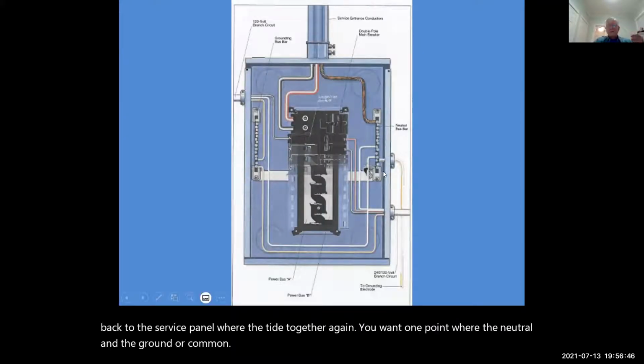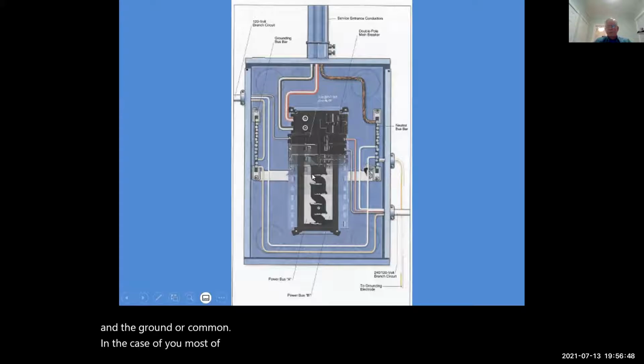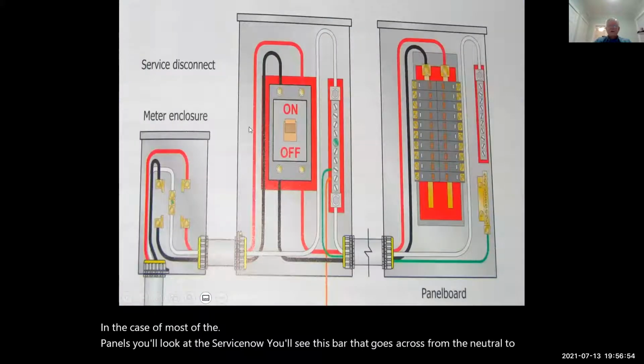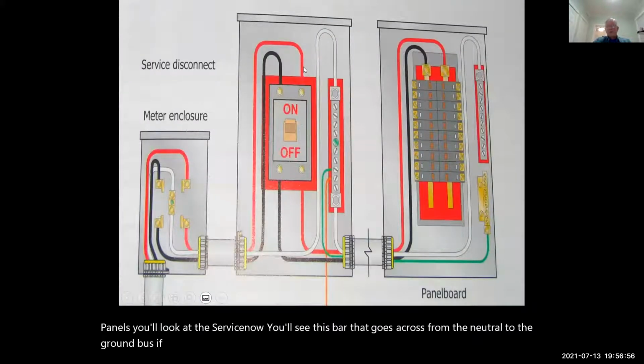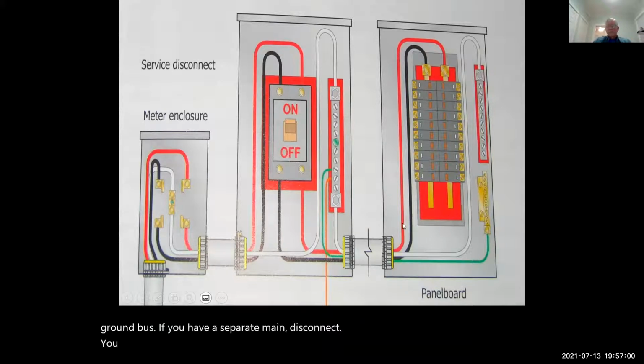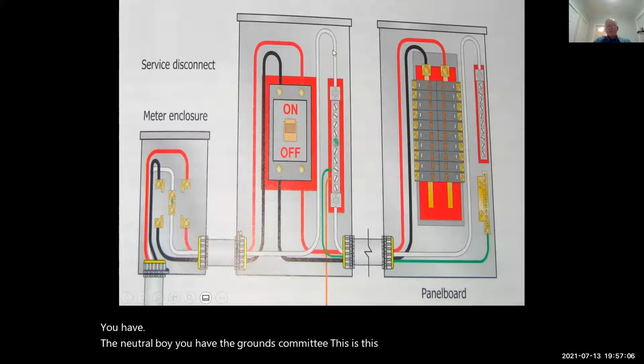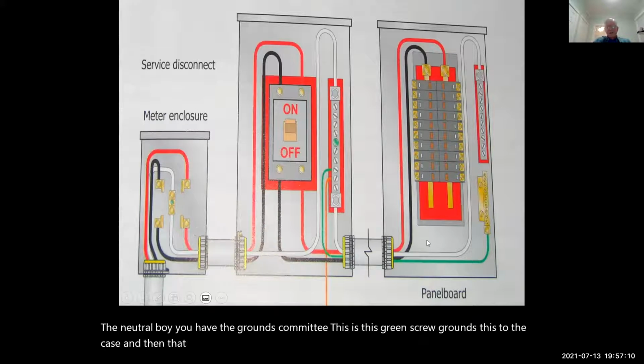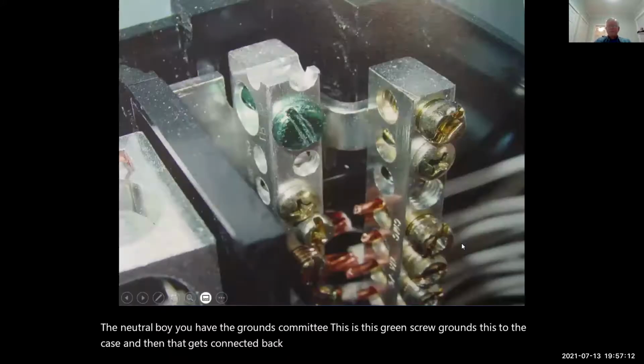In most of the service panels you look at, you'll see this bar that goes across from the neutral to the ground bus. If you have a separate main disconnect, you have the neutral bar, you have the grounds coming in. This green screw grounds this to the case, and then that gets connected back here. So you have that single point.